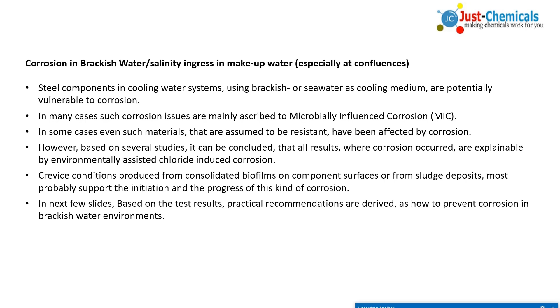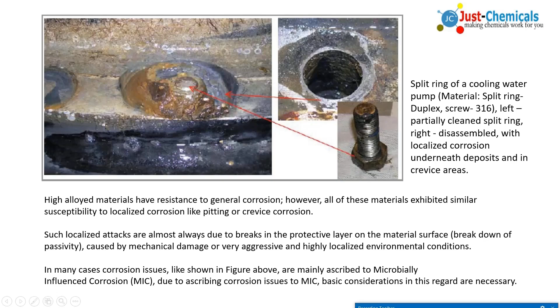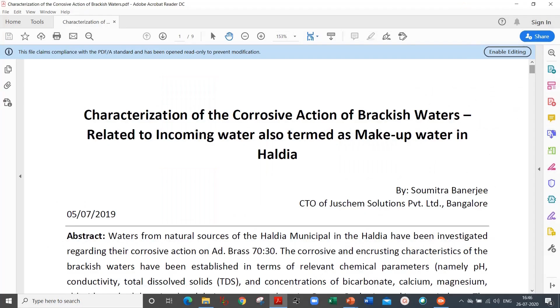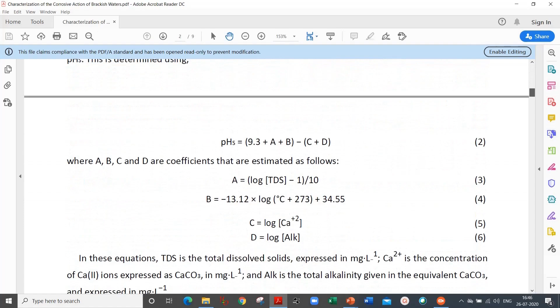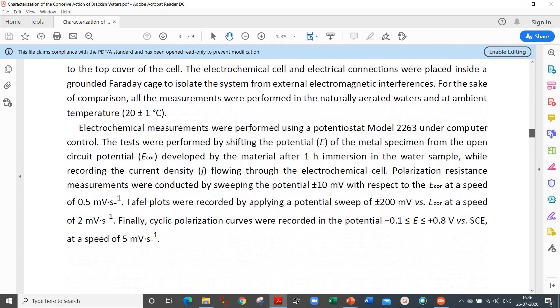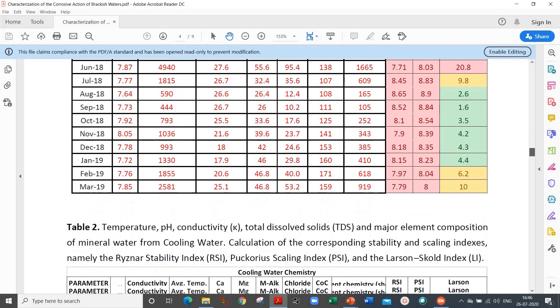Every 1 meter is having 2 pinholes, and that is caused by SRB. There are smuts and nodules on the pipeline, which I removed. I smell sulfide, a rotten egg smell, and pit formation starts. Like this, pit formation will start. When I send this, it has all the related results, how it was measured and how it was done, and all the RSI, PSI, Larson index, everything was done on makeup and cooling water.